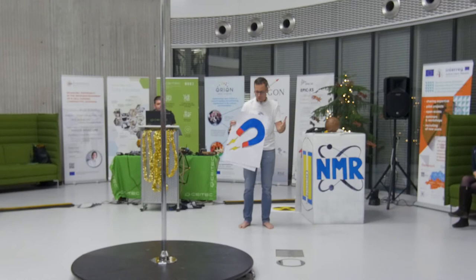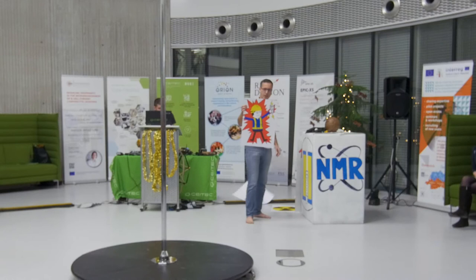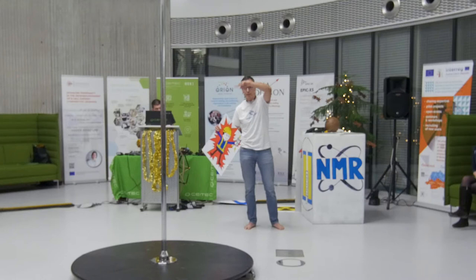We have 22 or 23 Tesla in the strongest magnets. The only problem is resonance — for example, when we were at the Kutlarska campus, there was a lot of resonance, but not from the magnets: from the tramways and trolley buses going around. So we had to deal with that somehow.